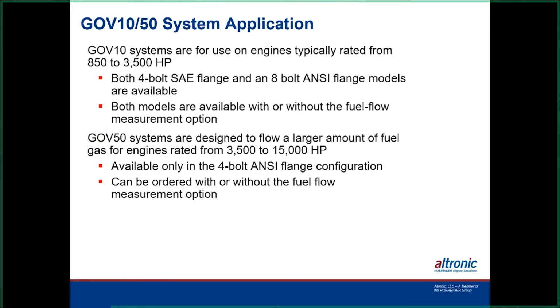The GOV10 is a smaller one. It's the one utilized mostly. Very few GOV50s are out and about out there, and normally if they are, it's because the fuel supply pressure was low, so we needed a valve with a bigger poppet in it to get gas to the engine. The 10 comes in either a 4-bolt flange or an 8-bolt flange. And then the 50 only comes in a 4-bolt flange.